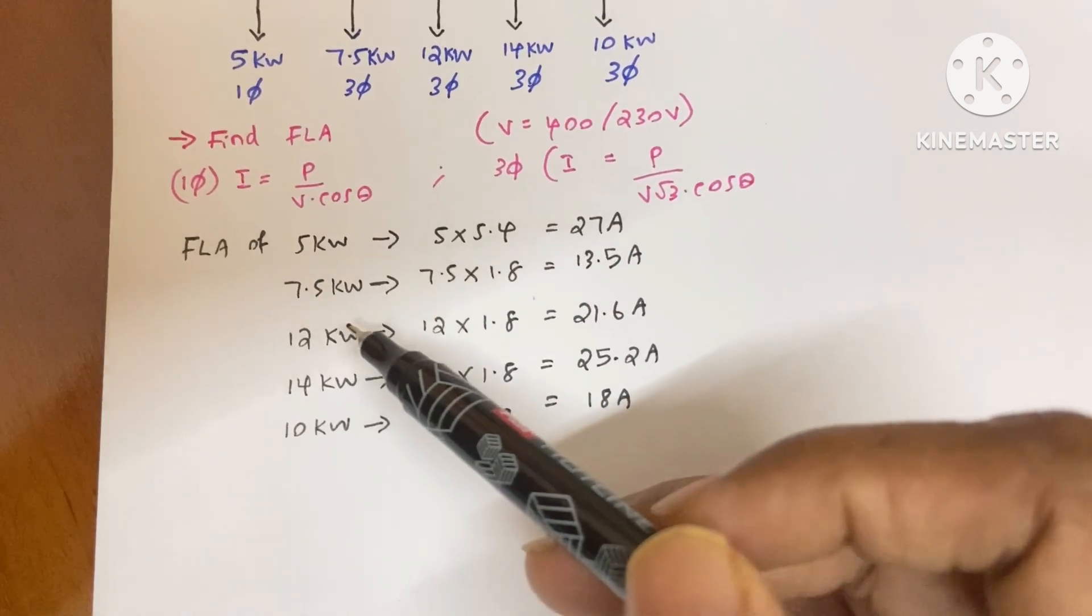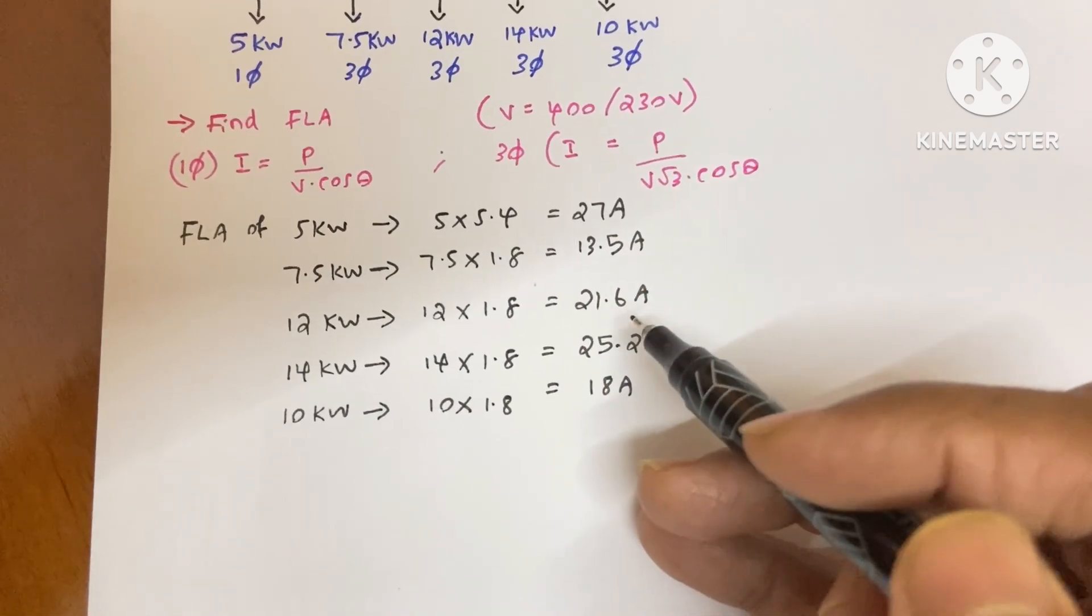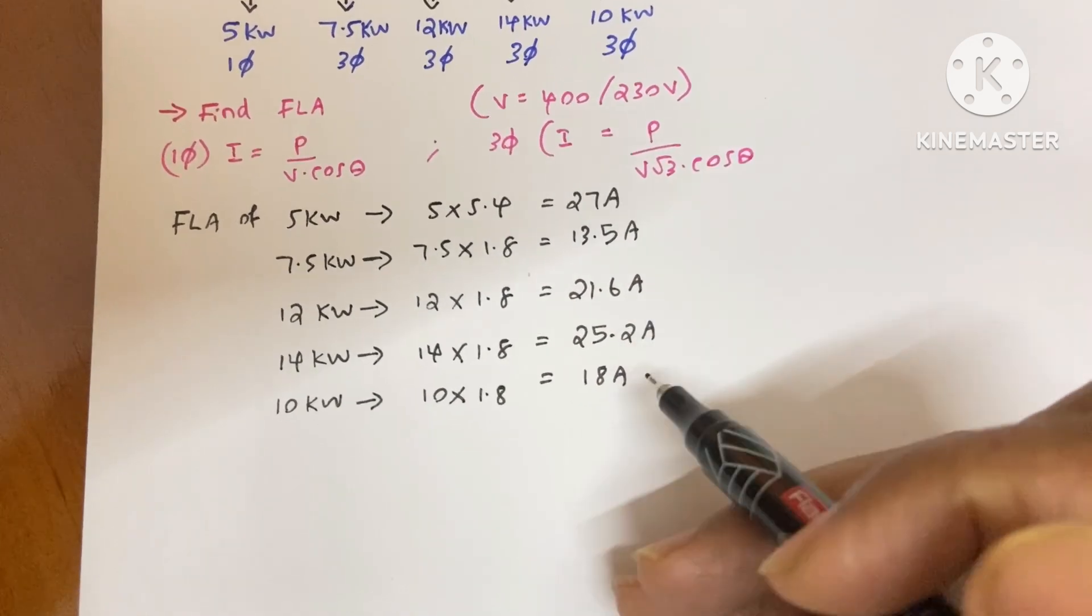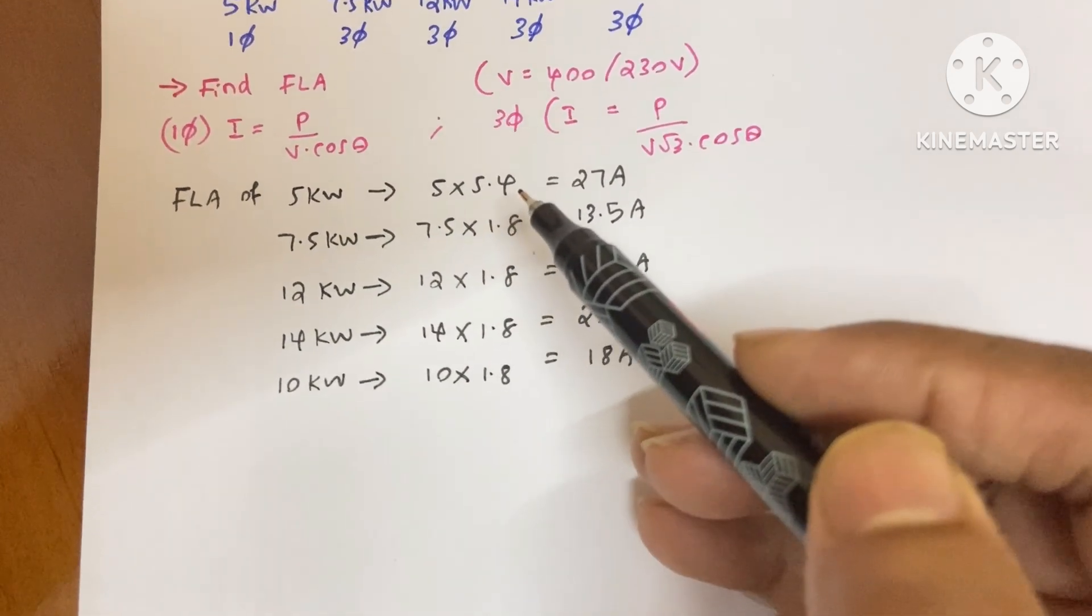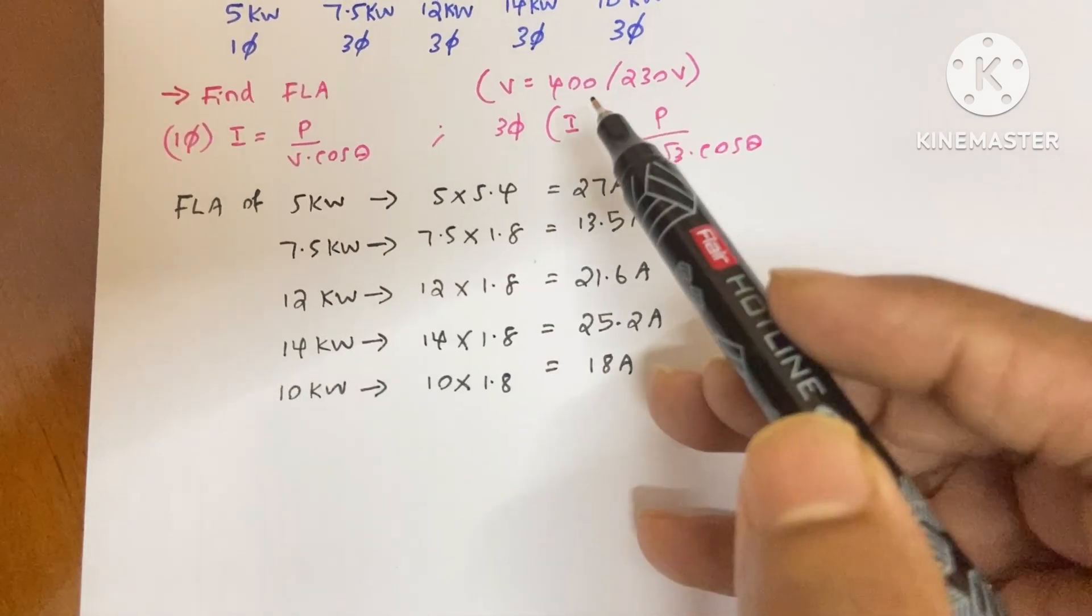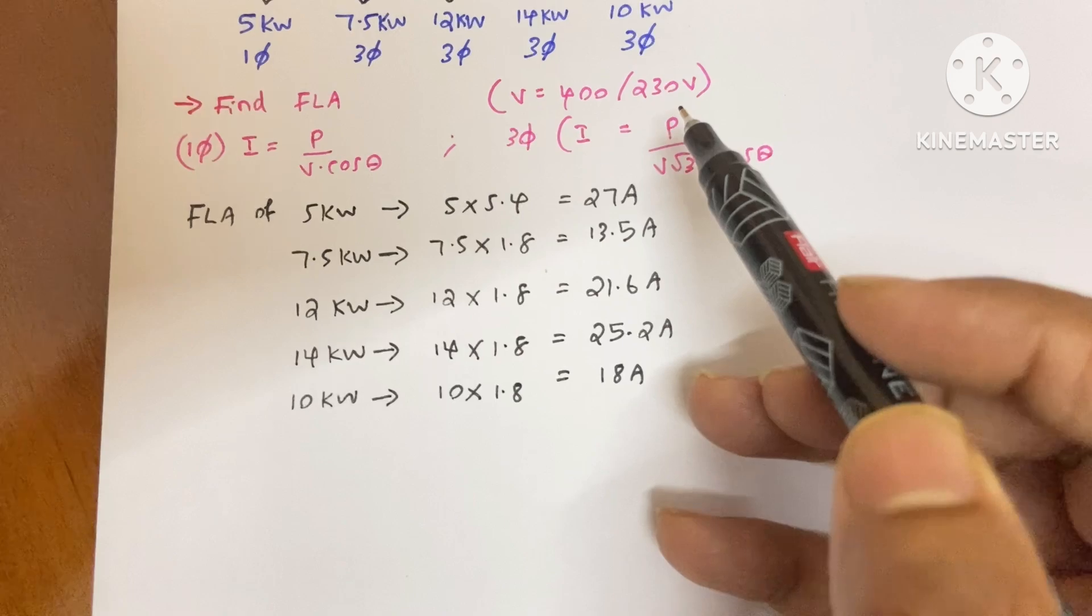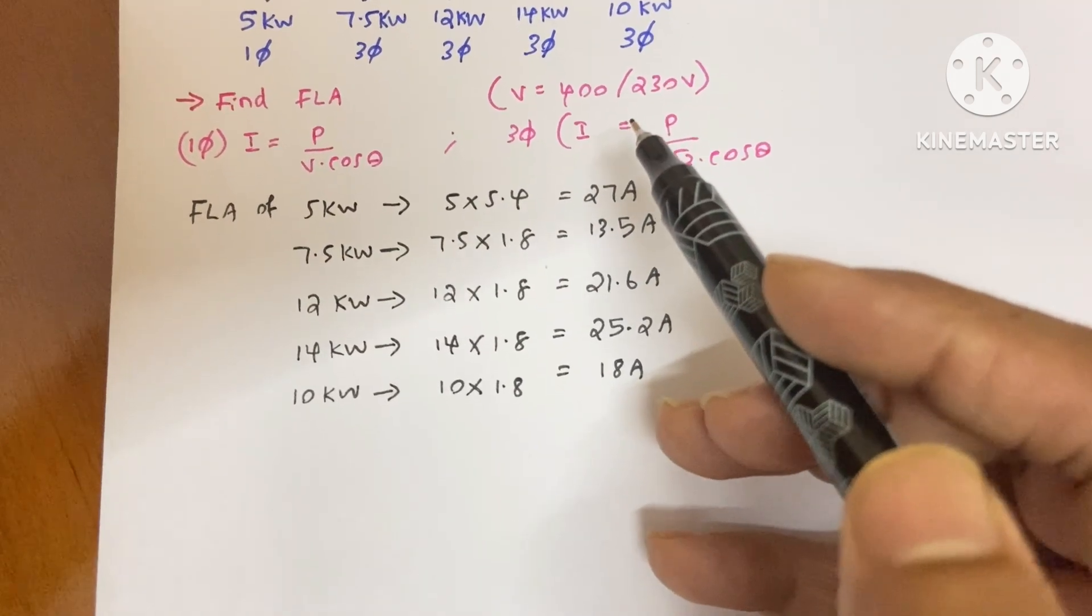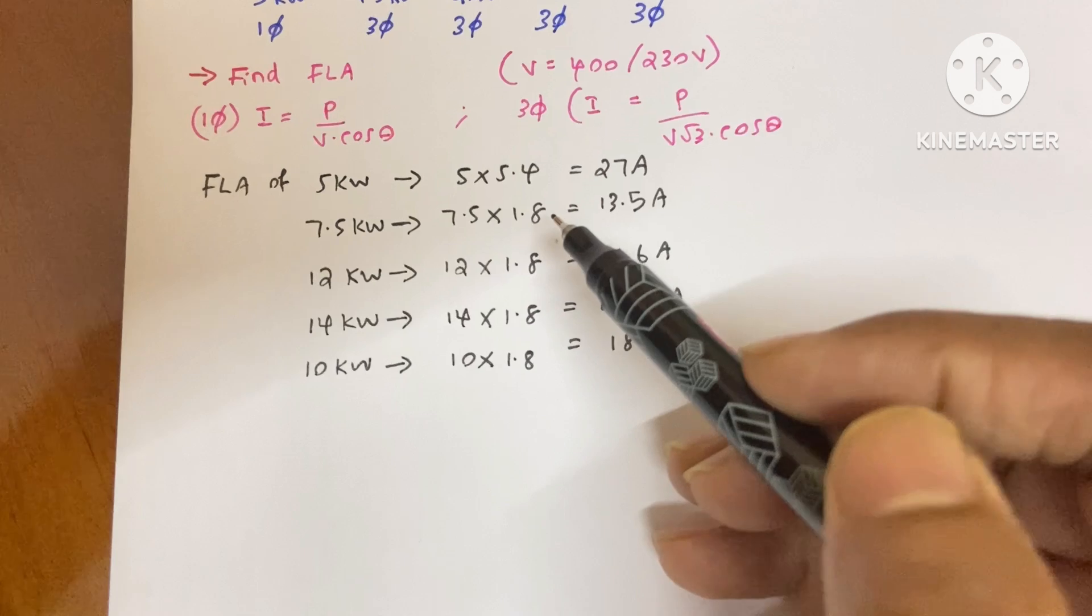Just like that, for all other motors we already got the full load ampere of these values. You can use these magic values of 5.4 and 1.8 if your voltage is 400 by 230 volt. I already made a video of how to find this 5.4 and 1.8, so if you visit my channel you will get that video.